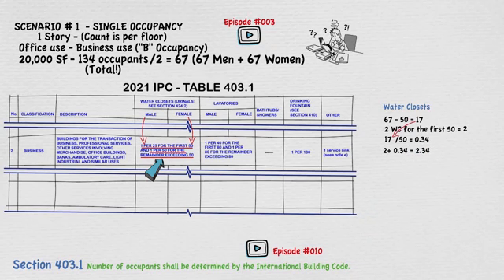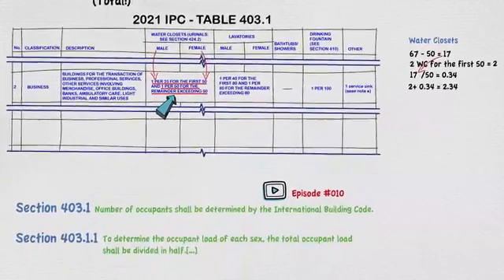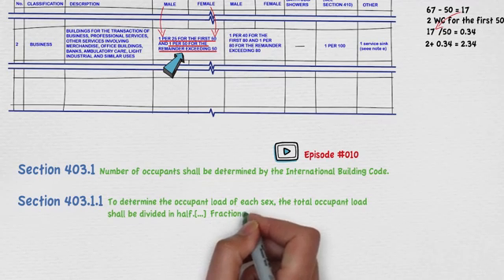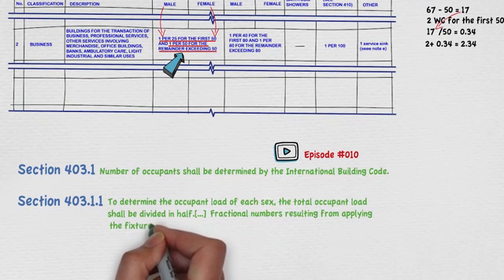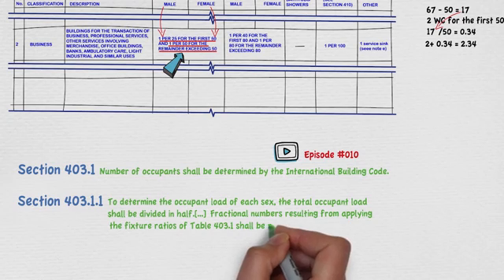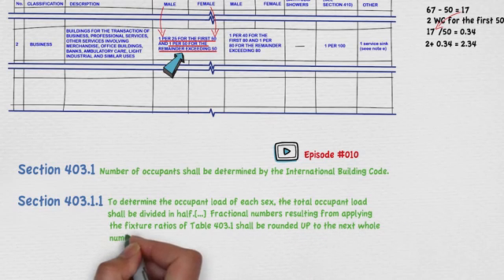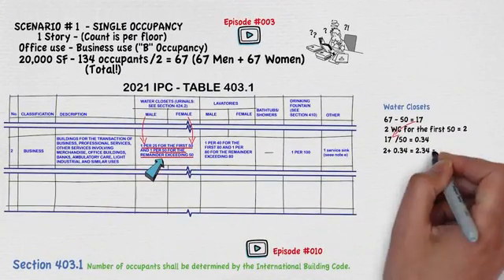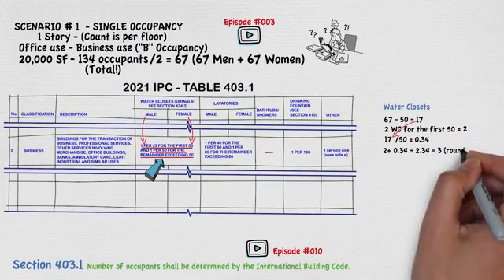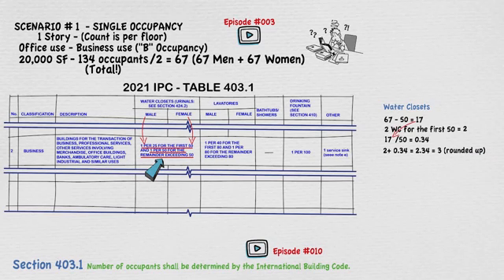Obviously we cannot have 0.34 water closets. Section 403.1.1 states that fractional numbers resulting from applying the fixture ratios of table 403.1 shall be rounded up to the next whole number. With this stated, our 2.34 gets rounded up to 3. So now we know that male and female restrooms each require 3 water closets.